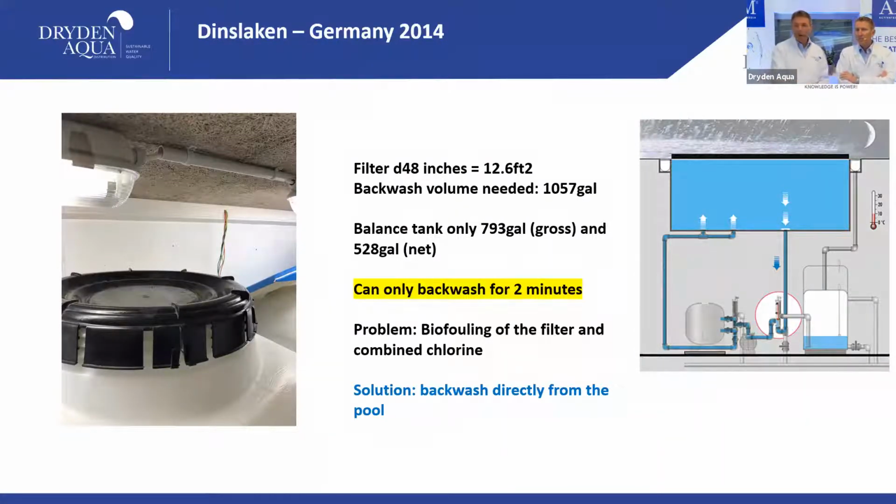Now remember, our DIN filters are 2 meters. So if you want to backwash them at the right velocity, you need 3-4 minutes until you get from the nozzle plate or from the laterals to the top diffusers. So 2 minutes is not enough. Philip made this calculation. That was in session 3? No, that was session 2. Session 2. Yeah, Florent, he's our genius. It's just not enough. So he said, but I do it 2 times. No, it's not helping. You really have to do it in one step.